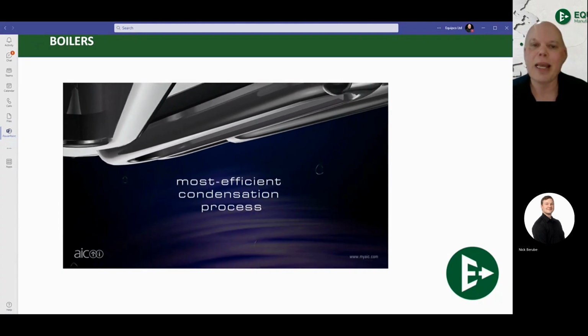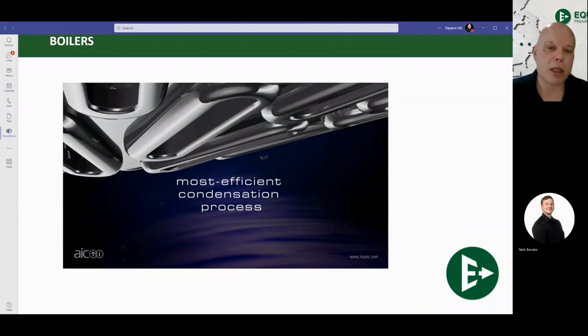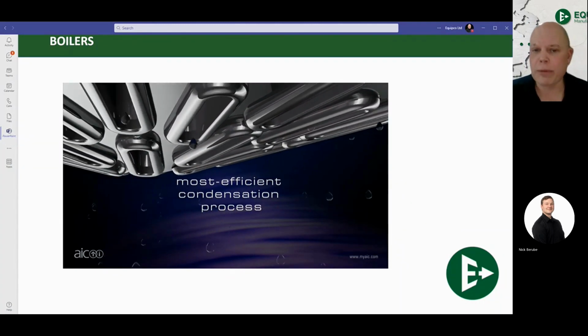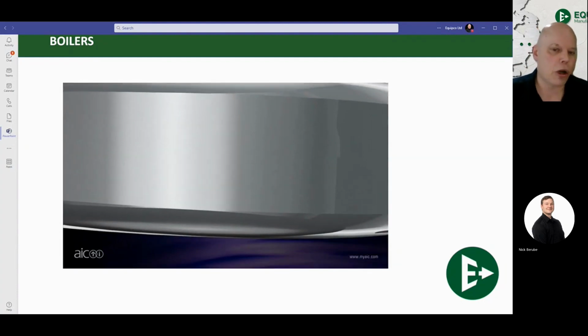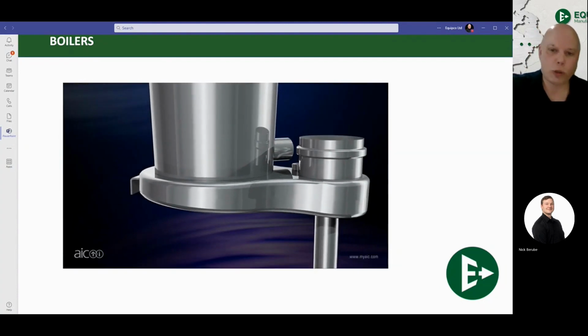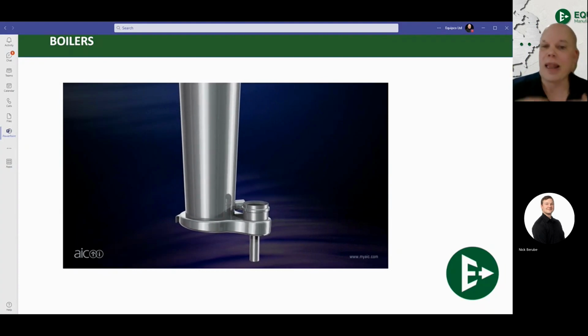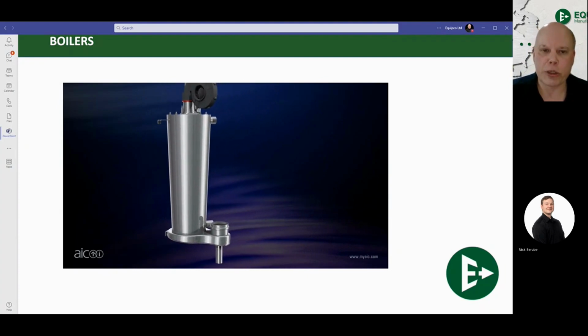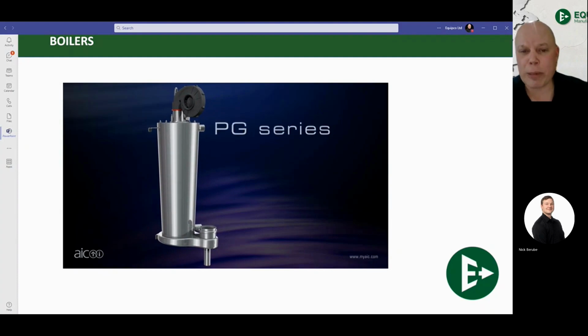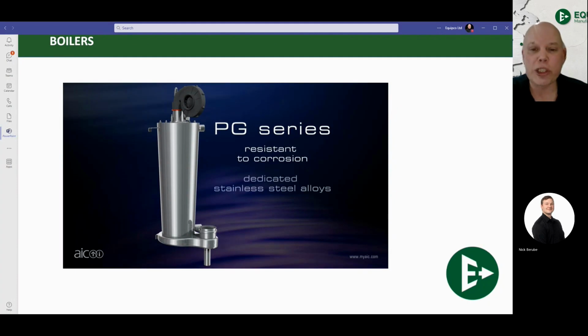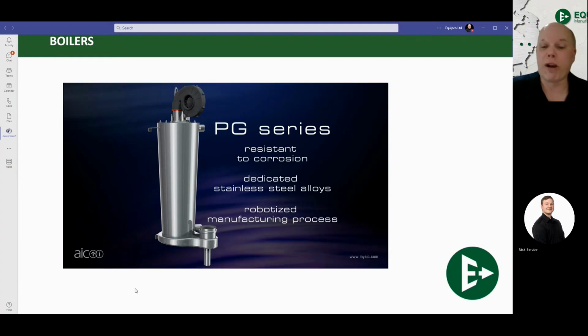Again, it is mildly acidic. It gets picked up inside the drain pan at the bottom, or the collector, whatever you want to call it, and that's designed to evacuate that condensate into one side and have your flue gas transfer over to the other side, up and out. And that is your standard fire tube heat exchanger. A couple things to note: extremely low head loss or friction loss through one of these. It is a real big open chamber. Water can flow through it quite easily. It does an extremely good job of heat transfer and is made to last a very, very long time. That's your standard fire tube heat exchanger.